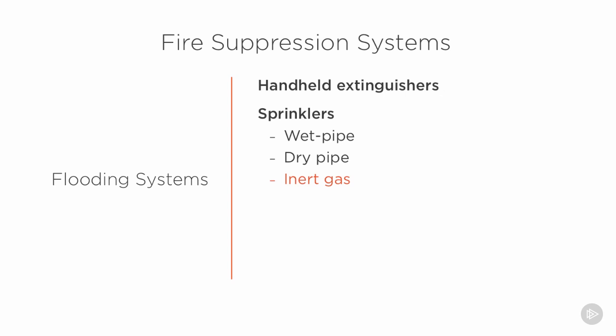That's the only problem with it. And that's not the only problem. The other problem, of course, is that halon destroys the ozone layer. It's a chlorofluorocarbon. And so halon production was actually banned by the 1987 Montreal Protocol. And you will still see some buildings that may have halon extinguishers. Most of them have been removed, but today, if they have a gas-based flooding system, it's usually going to be carbon dioxide or maybe something like argon or some of the other inert gases.